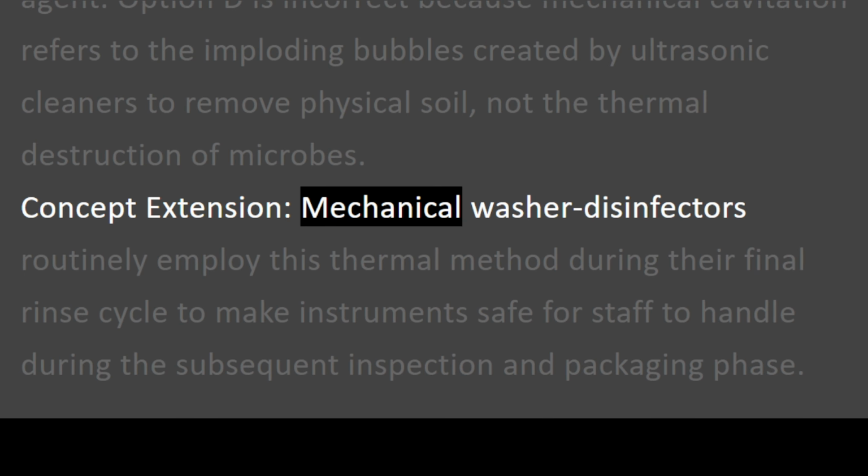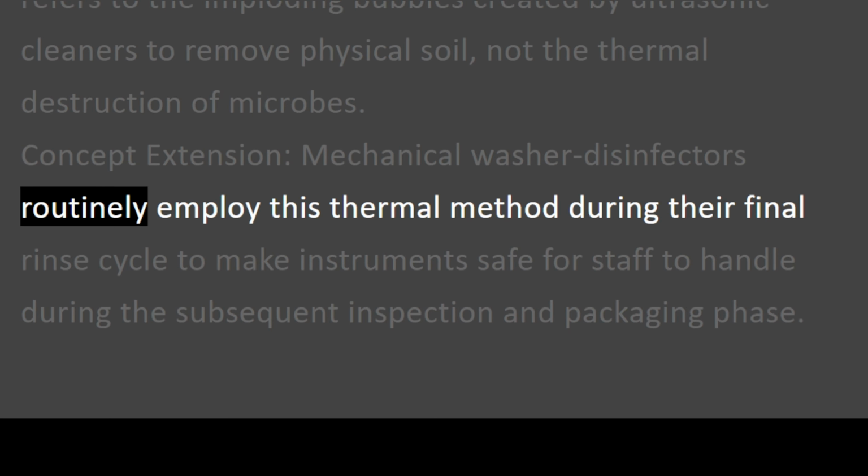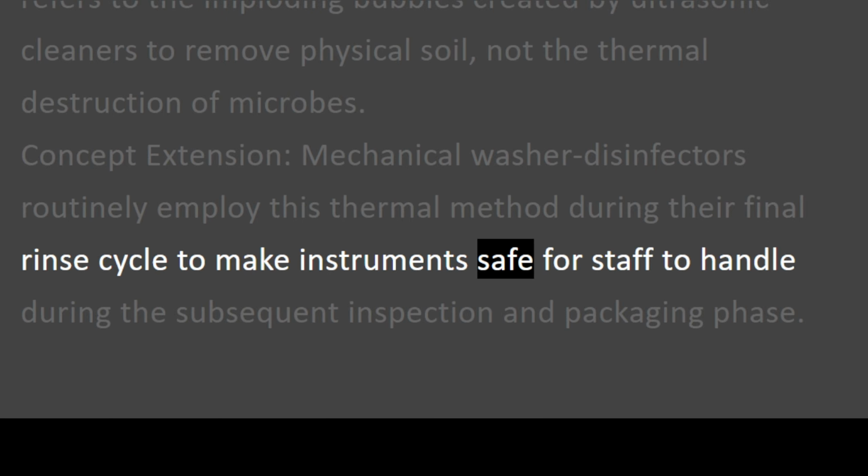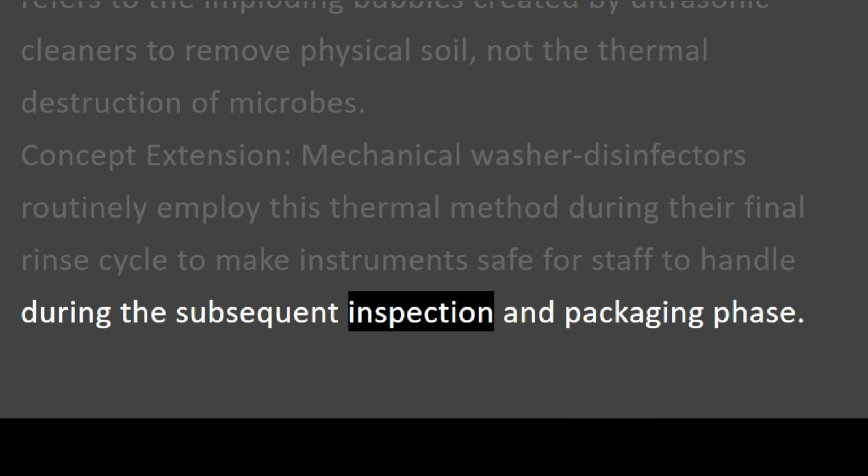Concept extension. Mechanical washer disinfectors routinely employ this thermal method during their final rinse cycle to make instruments safe for staff to handle during the subsequent inspection and packaging phase.